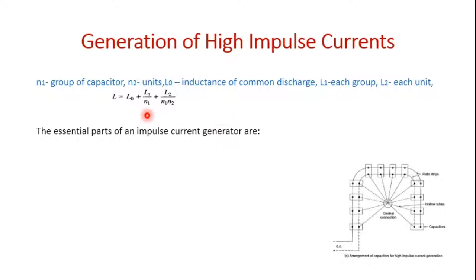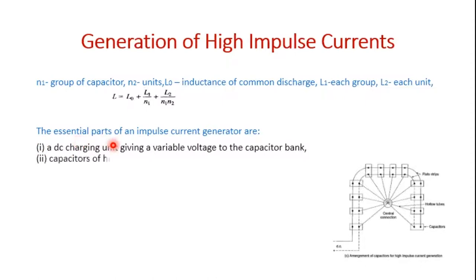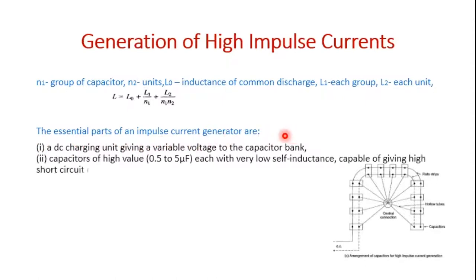The essential parts required for the impulse generator are: first, a DC charging unit giving a variable voltage to the capacitor bank, which is the input required for charging the capacitors. The capacitors, generally of 0.5 to 5 microfarads each with a low inductance value, should be capable of giving high short circuit current.